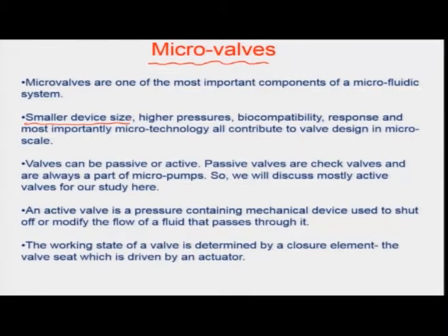When we talk about such microvalves, there are challenges like very high pressures. With small sizes and higher pressures, you are able to block the flow in normal conditions, so that the design really has to be very, very robust. There is also an issue of sometimes biocompatibility, because microvalves and microflows are typically used for diagnostic industries, and they find a lot of applications.